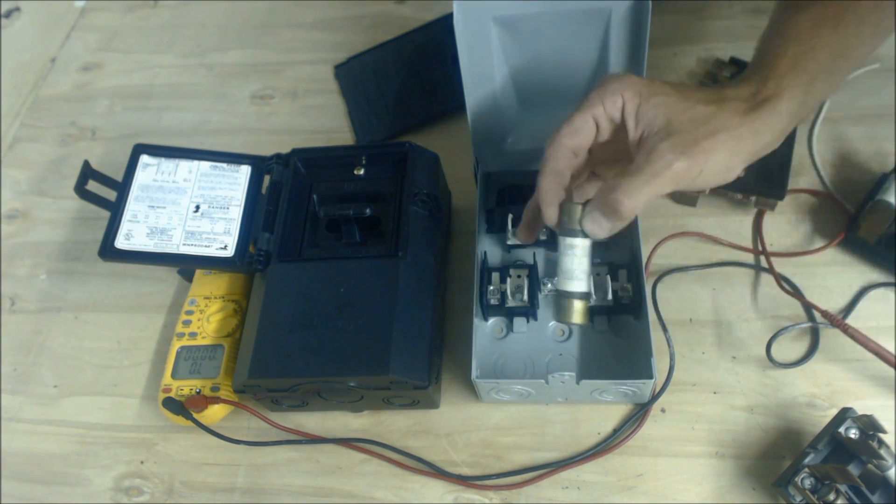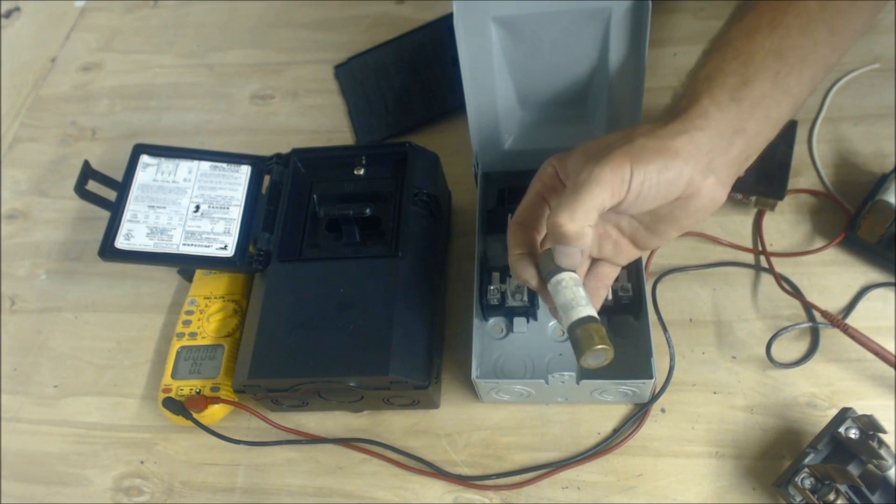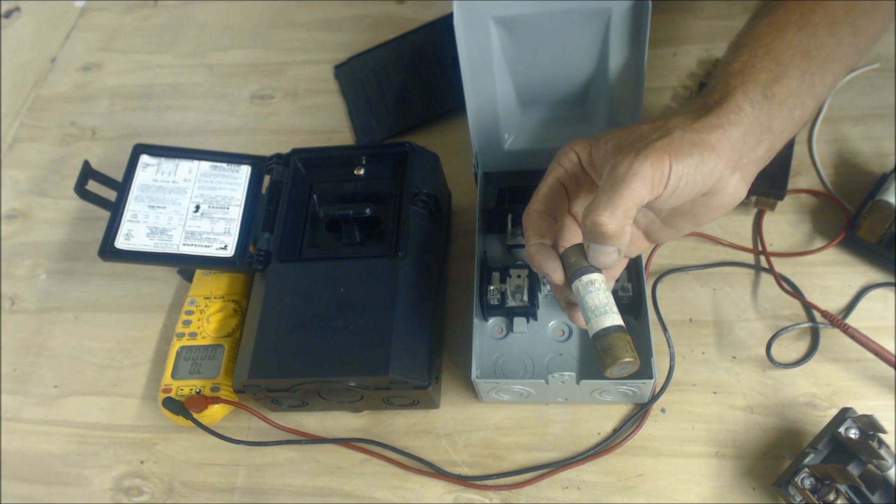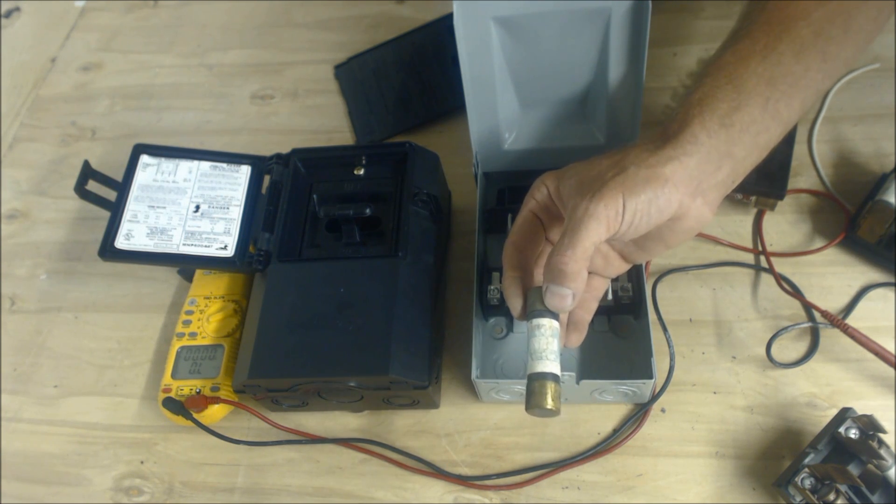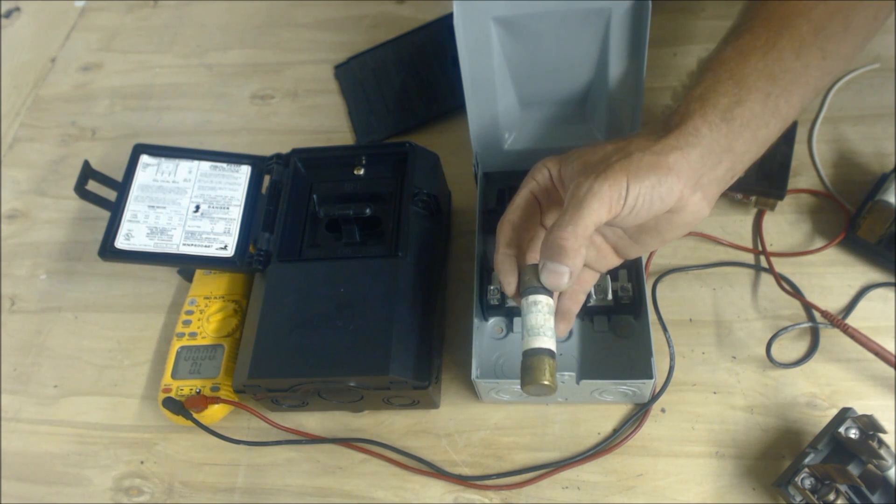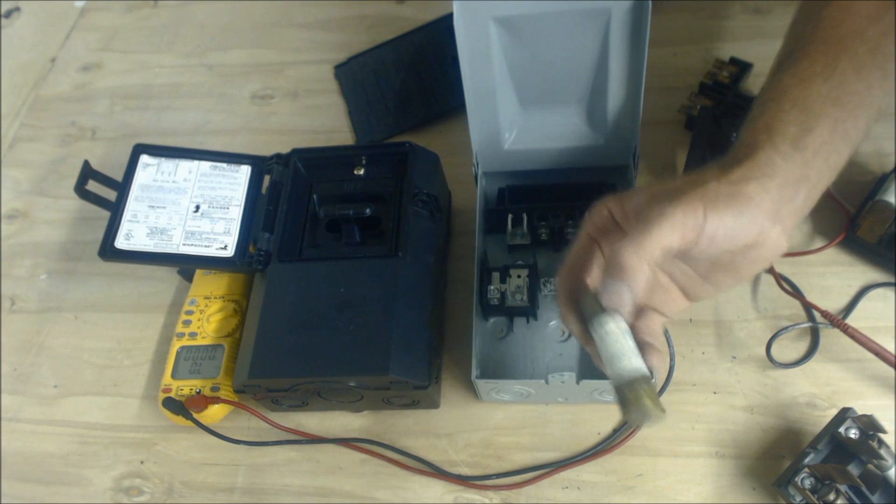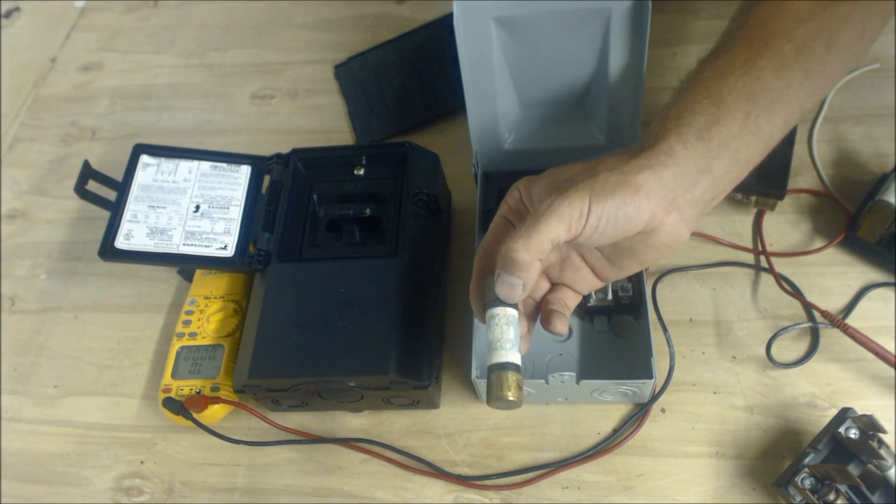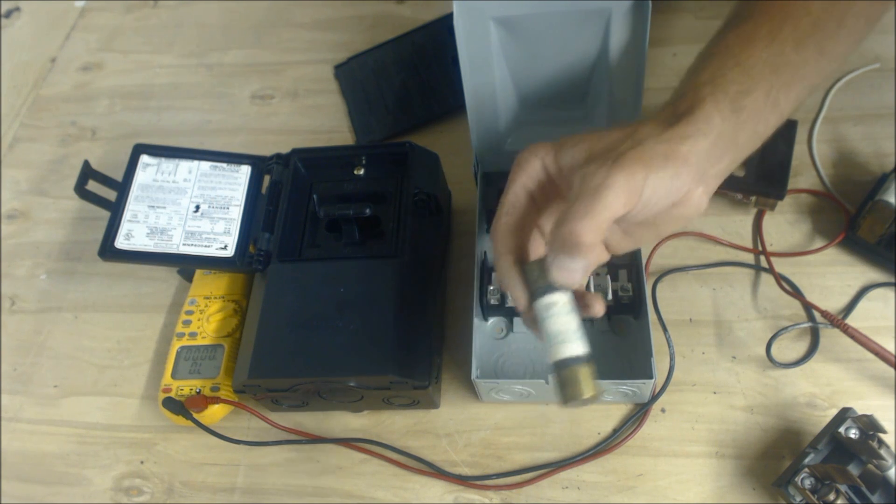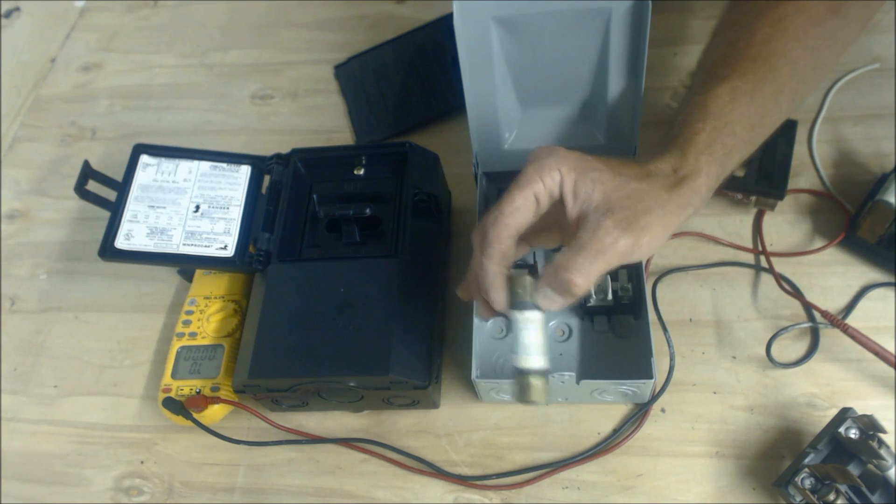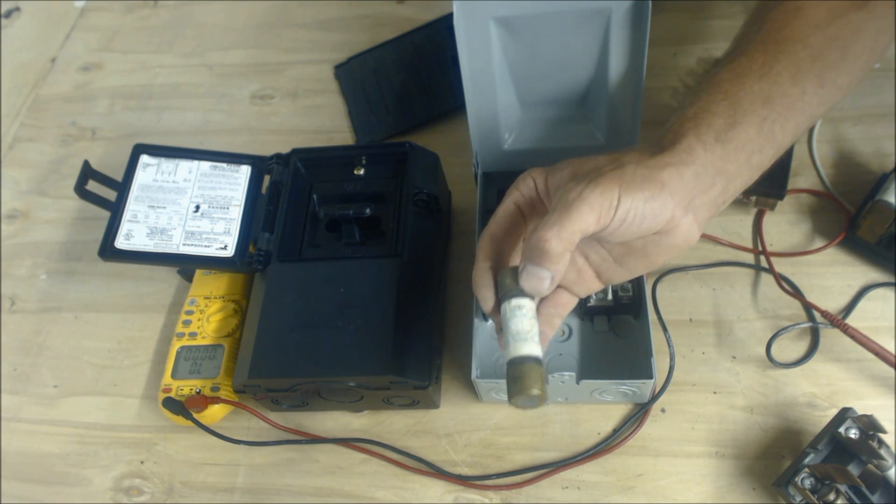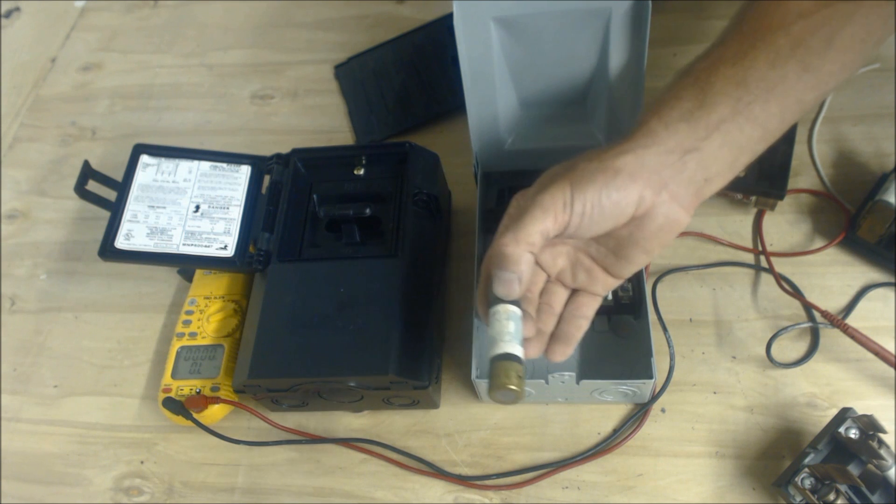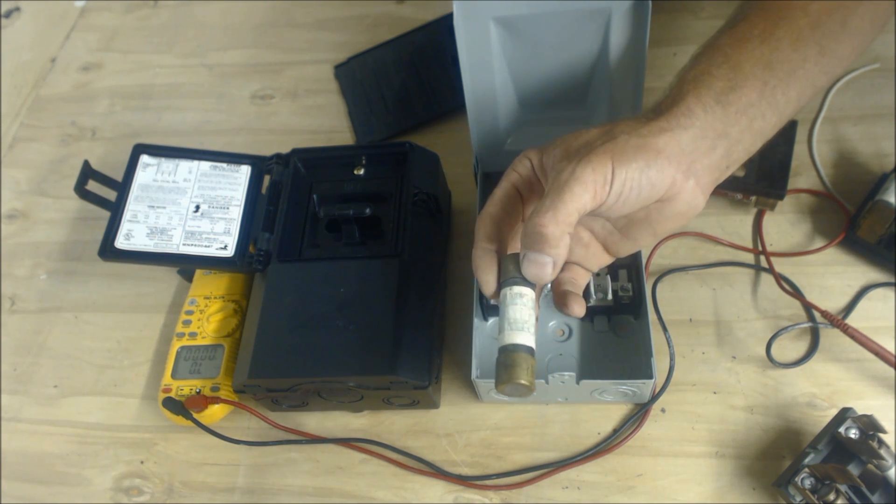But I've gone to sites where just one have blown and not the other one. And it's to no fault of the system, it seems. Maybe there was low voltage one day, from the power plant or something like that. Maybe there was lightning, maybe some type of anomaly. But I will tell you that I found plenty of bad fuses in the disconnects, just one, one of the two, bad. And I'll start it up and there's really no problem, and I don't get a call back after I replace it with the same correct amperage.